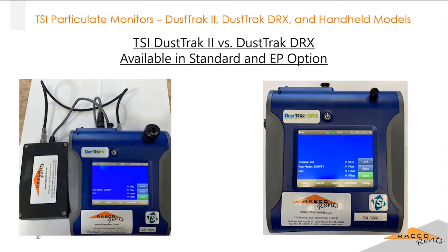There is a zero calibration that can be done by the user. So there's a zero filter you put on the inlet and you can do the zero calibration. That's going to make sure that you get your baseline of zero, to make sure that you're not getting negative readings or readings above what they should be when they should be zero. And sometimes that calibration can fail.